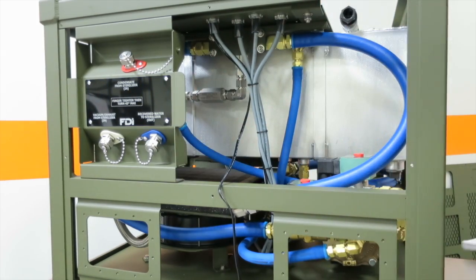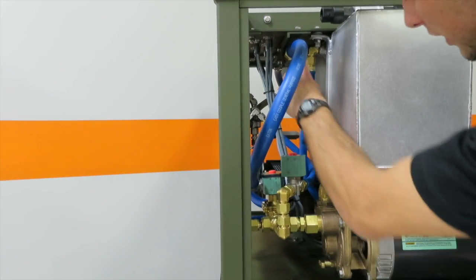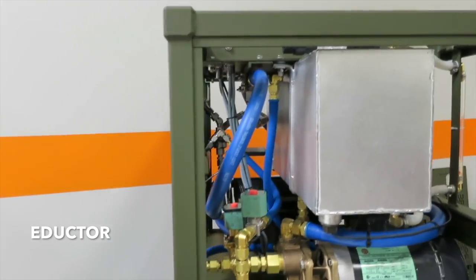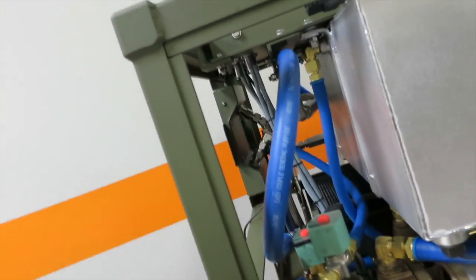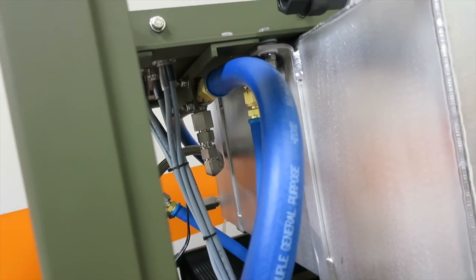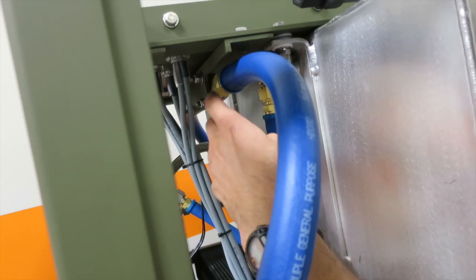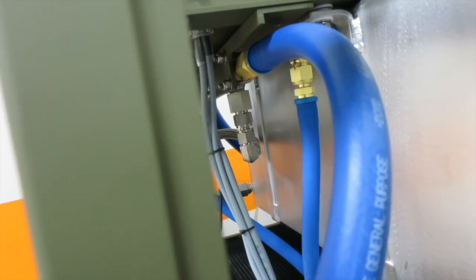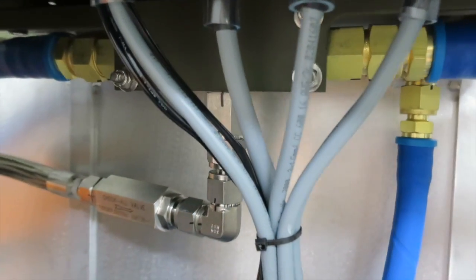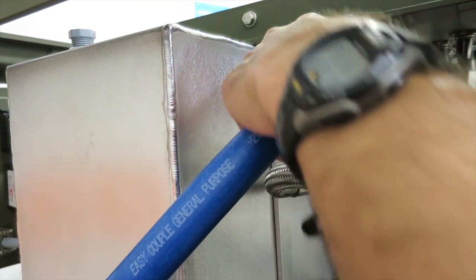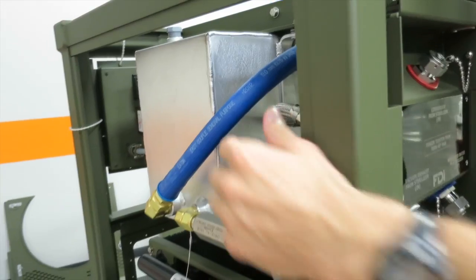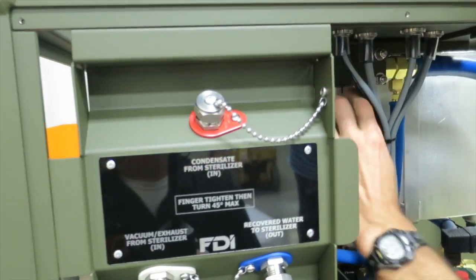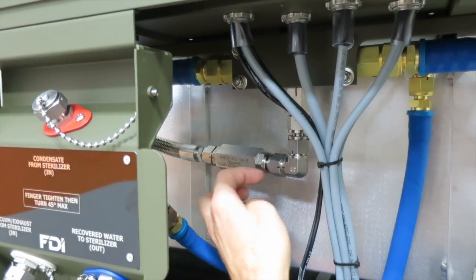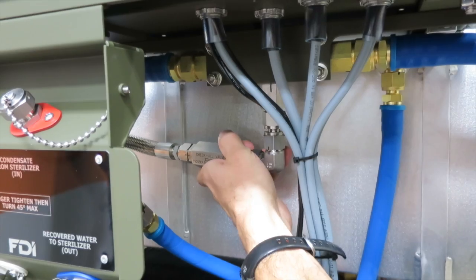Right here behind this bracket, we have the EDUCTOR. The EDUCTOR is what is creating the vacuum in the water recovery system. We have water rushing through this hose and through the EDUCTOR, going through a little nozzle that's creating the low pressure and creating the vacuum on this bottom side. On this side you have the outlet that's flowing back into the tank. Again, the pump is pumping water through the EDUCTOR, and it's creating the low pressure here, which creates the vacuum that pulls on the chamber of the sterilizer main unit.